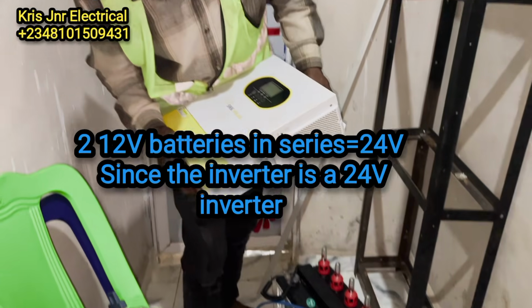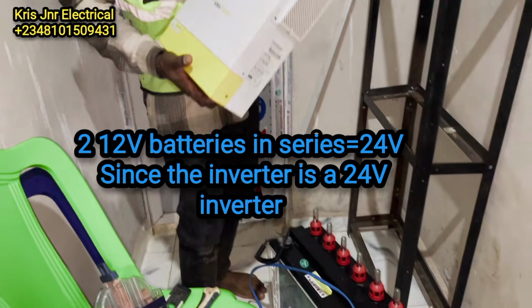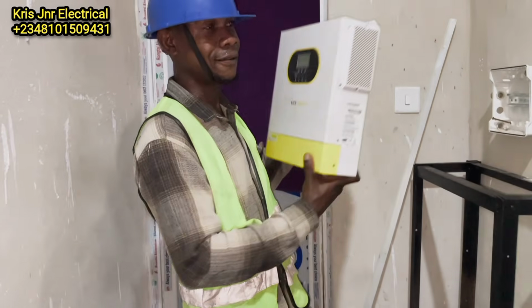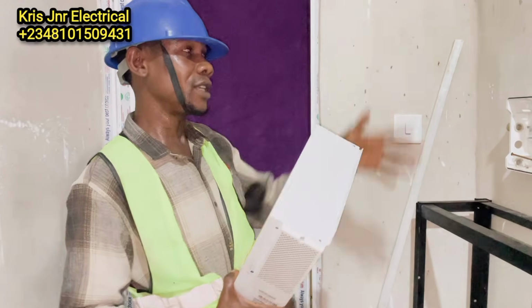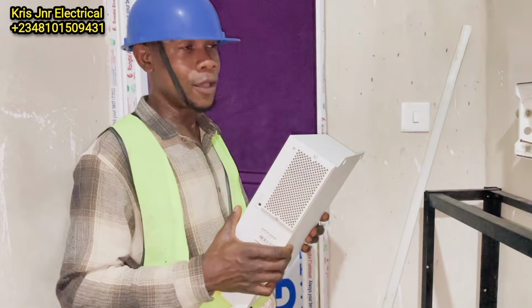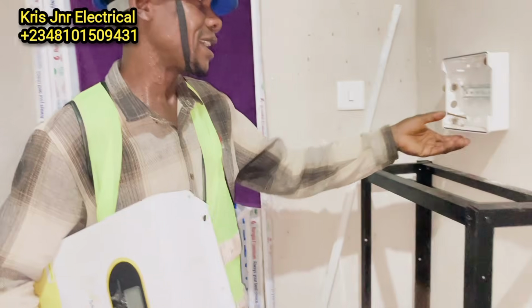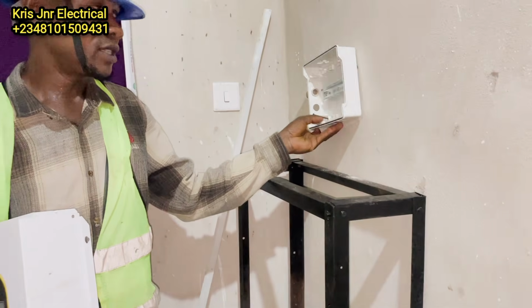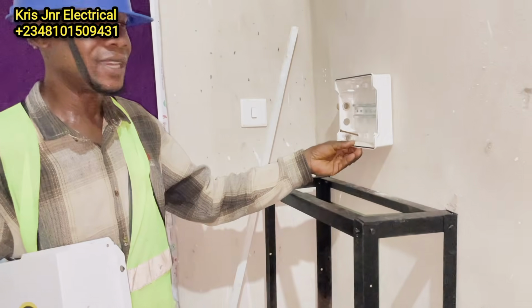So these are the batteries. We are going to use two 12-volt batteries. This is a 24-volt inverter. Take note, you must read the nameplate very carefully before you install the inverter. You must be conscious of the voltage of the inverter and match the battery voltage to the voltage of the inverter.